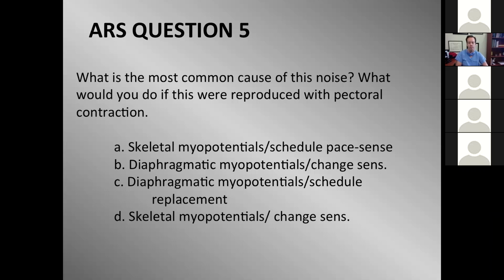Let's say it's a chatter that looks like a conductor fracture. So you're asking if you notice noise on the pace sense circuit only, and everything else is fine, high voltage impedance is fine. Are you asking, can you replace the pace sense lead, or do you have to worry that the whole thing is crummy and replace everything? Or could you reprogram them?